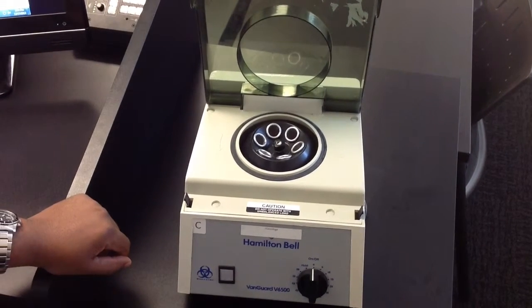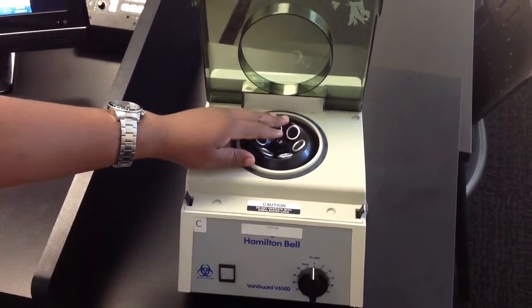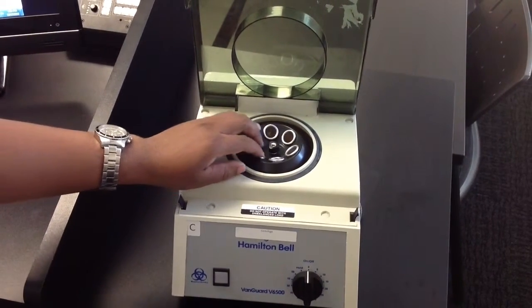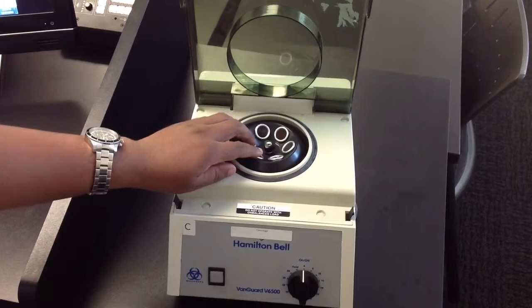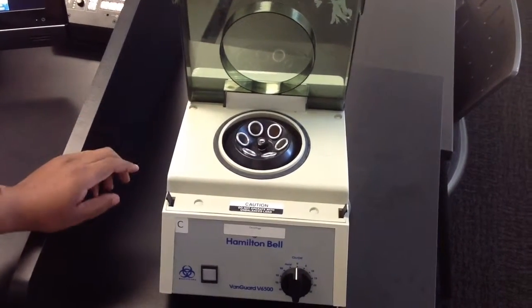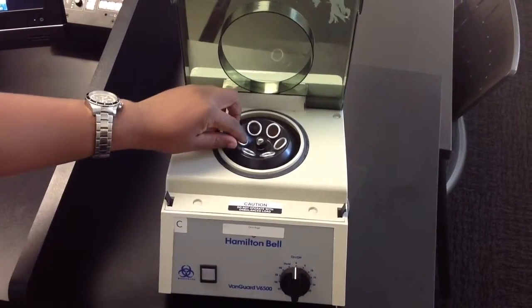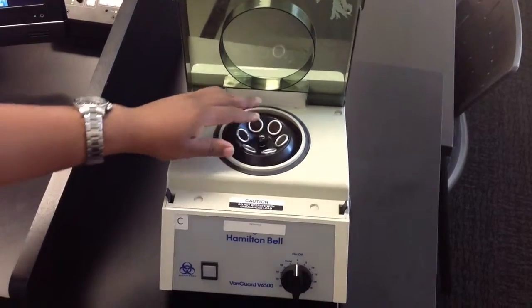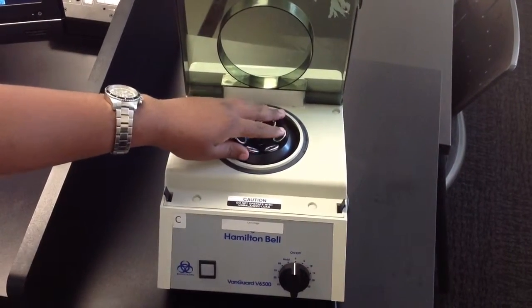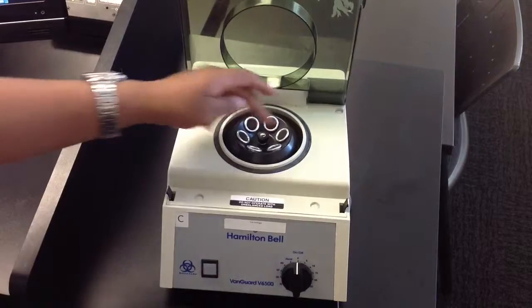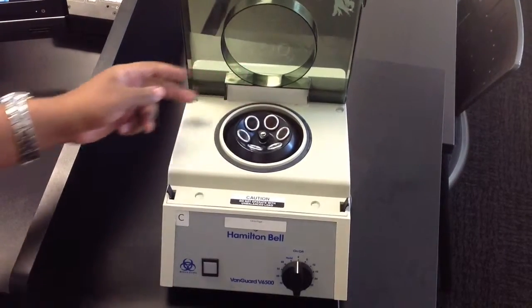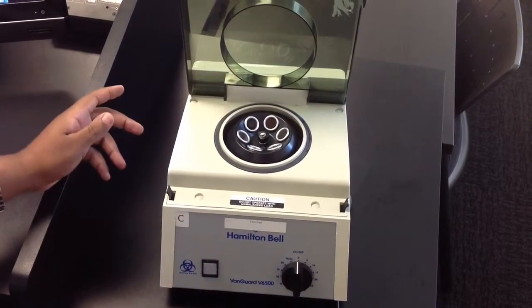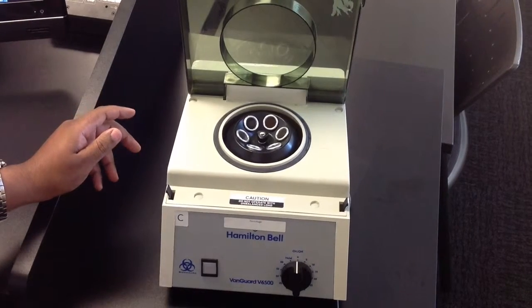100,000 rpm. Now, in the case of rotation, what occurs is centrifugal force, which is where the name centrifuge comes from. Centrifugal force is measured as the mass, being the sample, times the velocity squared, which would be the speed that the centrifuge is spinning, divided by the radius of the actual rotor, and that would determine your centrifugation, if you want to say it that way.